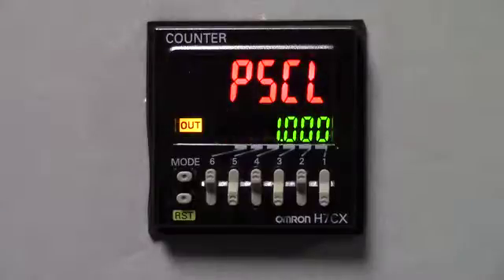We are going to press the mode key, which takes us to the pre-scale value. You would use this function as a way of scaling an input to equal a certain amount of counts on the display. A typical application would be using an encoder and needing to scale the display to read the number of feet or meters traveled.